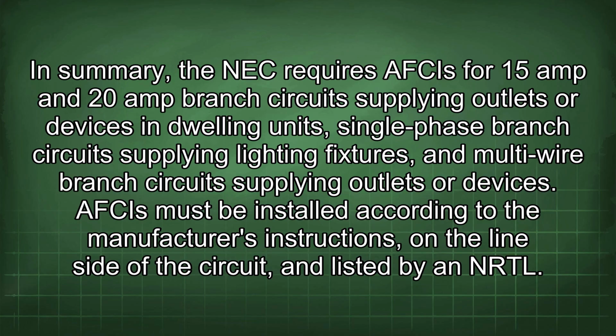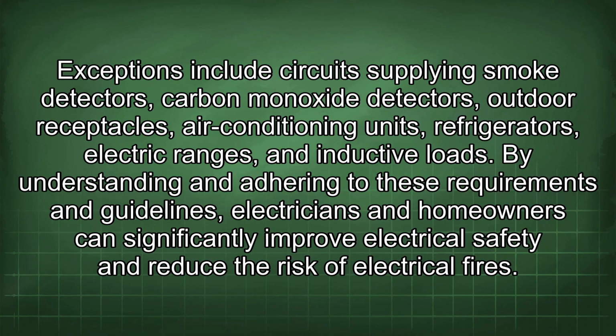In summary, the NEC requires AFCIs for 15 amp and 20 amp branch circuits supplying outlets or devices in dwelling units, single-phase branch circuits supplying lighting fixtures, and multi-wire branch circuits supplying outlets or devices. AFCIs must be installed according to the manufacturer's instructions on the line side of the circuit and listed by an NRTL. Exceptions include circuits supplying smoke detectors, carbon monoxide detectors, outdoor receptacles, air conditioning units, refrigerators, electric ranges, and inductive loads. By understanding and adhering to these requirements and guidelines, electricians and homeowners can significantly improve electrical safety and reduce the risk of electrical fires.